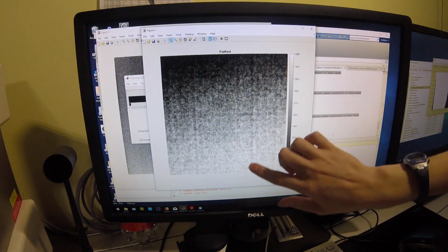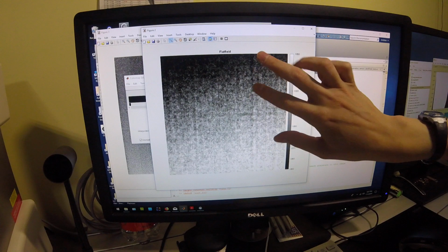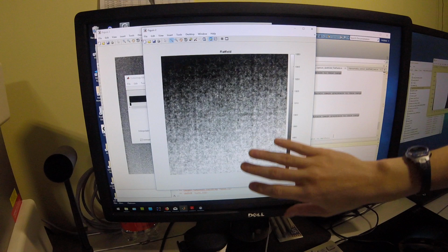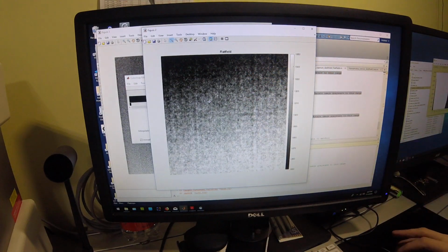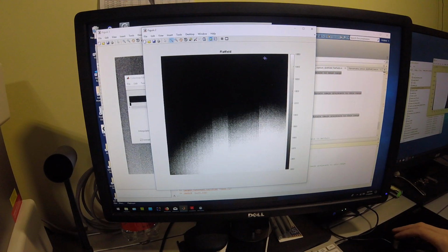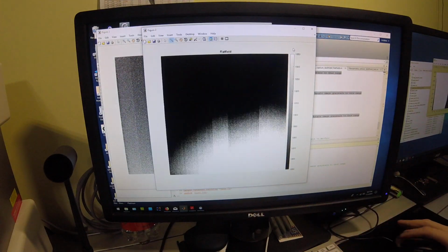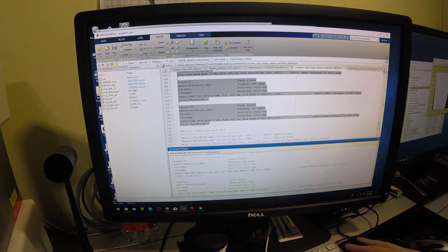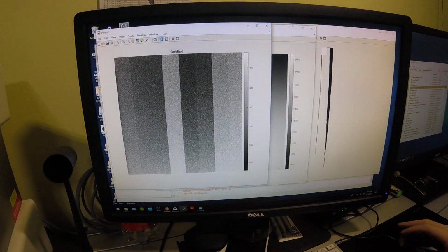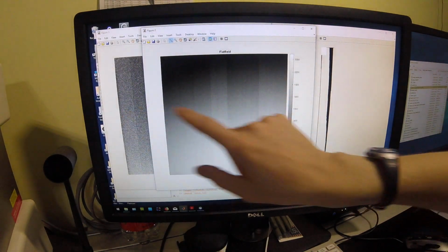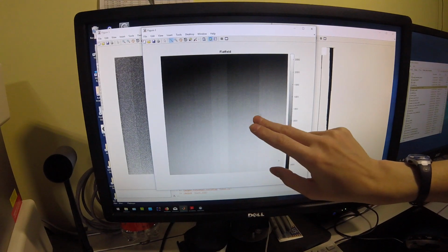And this is actually the X-ray absorption of that carbon fiber plate, that carbon fiber sheet that's used to protect the image sensor. And by performing that Flatfield Darkfield correction, you can remove both that Darkfield dark current and the Flatfield inhomogeneity in the X-ray sensitivity. You just remove that mathematically. You can also see that Darkfield variation showing up in the Flatfield image.